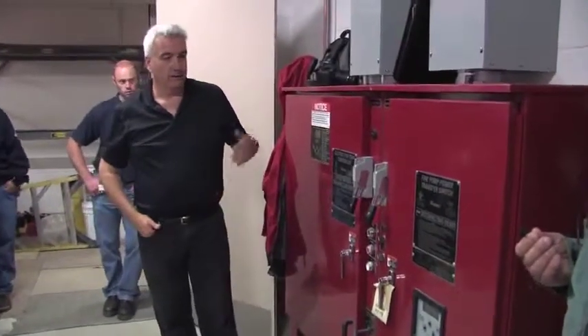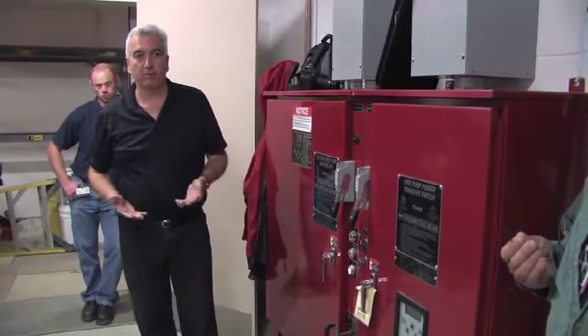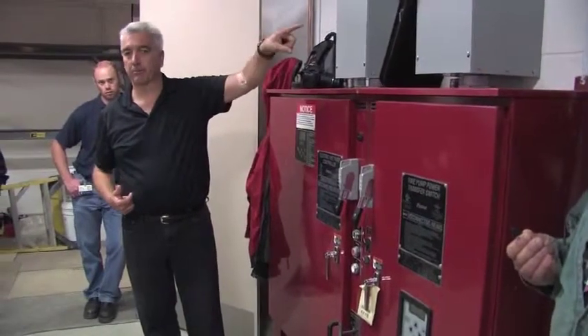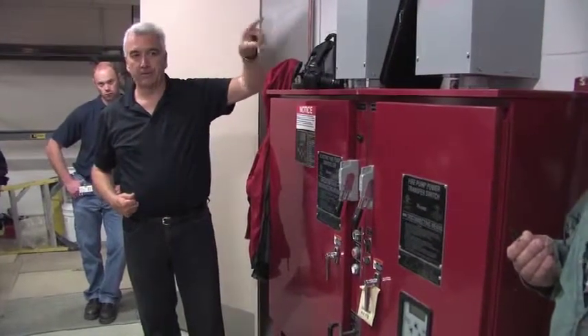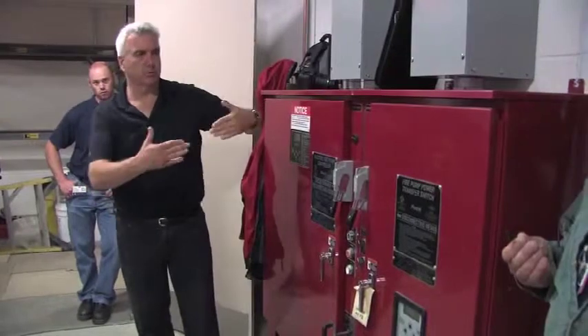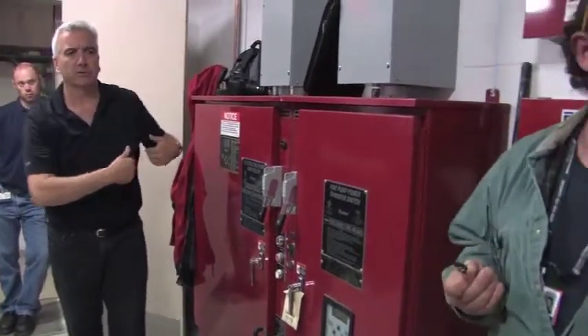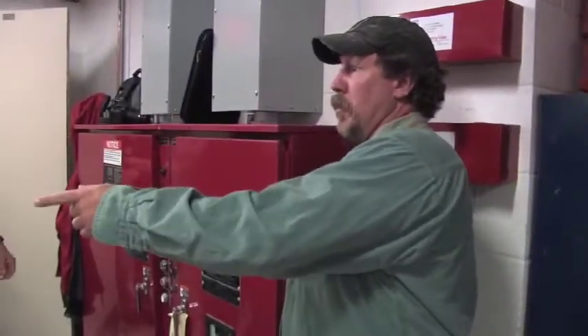So, I know you guys pretty much know how fire pumps work. You have a jockey pump controller that is a pressure maintenance pump. Then you have a high zone controller and a low zone. Which one's which one? I can't remember which one's which. This is for the turbine. Okay. And this one here is doing everything. Okay. All right.